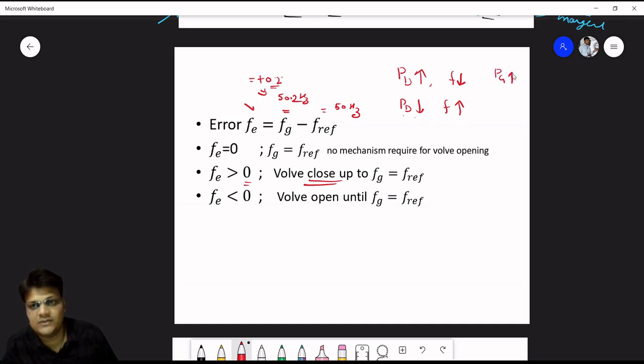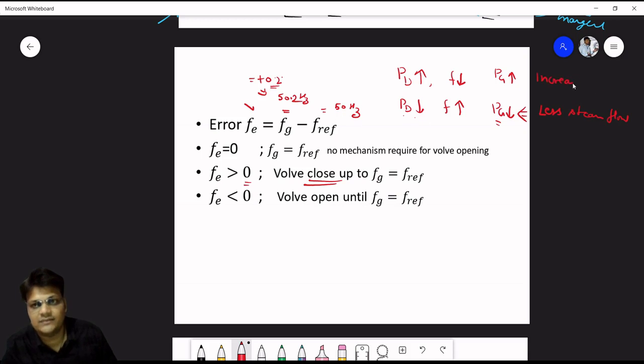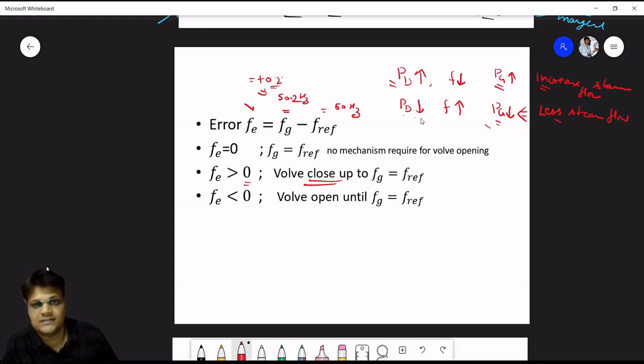When demand increases, we increase steam flow; when demand decreases, we reduce steam flow to reduce generation. The valve opens until the error equals zero — when Fg equals F_reference, no further valve action is needed. If frequency is below reference, we increase steam flow; if frequency is above reference, we reduce steam flow.